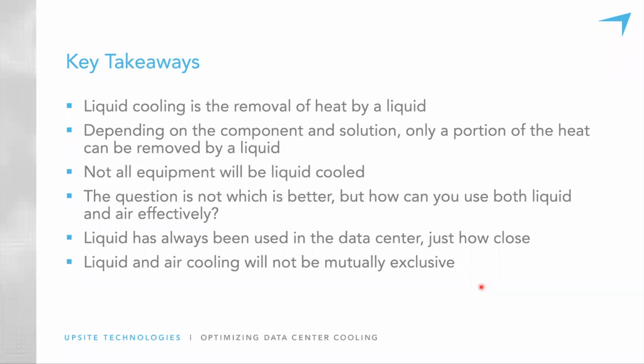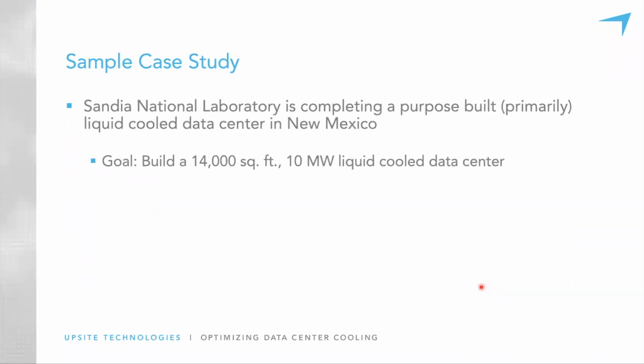But I'd like to share now with you the results of that question that we asked you before about the case study. So Sandia National Laboratory set out to build a purpose-built liquid-cooled data center. Their design considerations were 14,000 square feet and 10 megawatts of heat dissipation. And here's what people guessed. We had a couple people guessing they were able to pull off 100% liquid cooling. Most people guessed 85% liquid to 15% air, and then tapering out with lesser and lesser amounts of liquid.